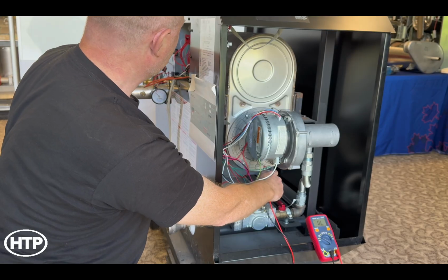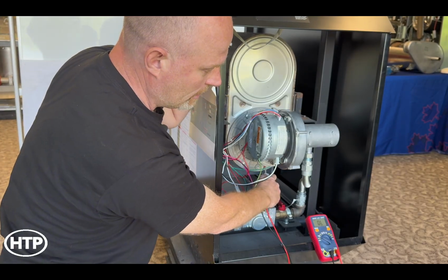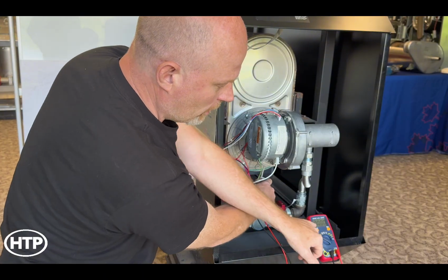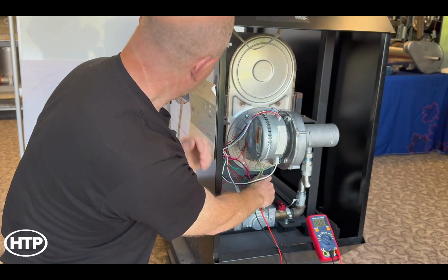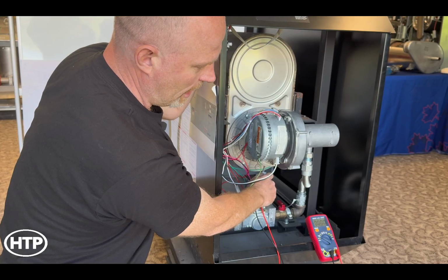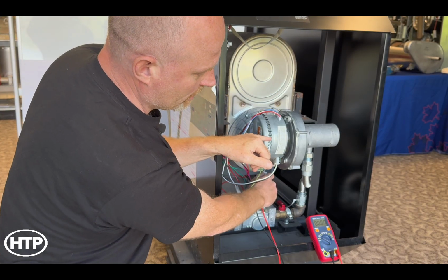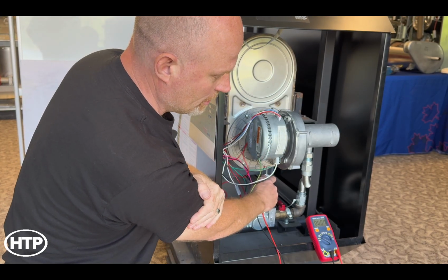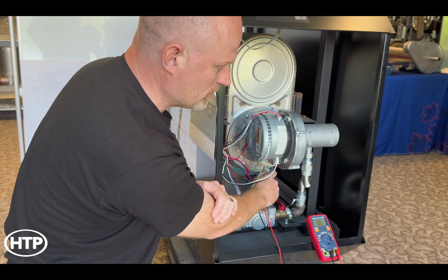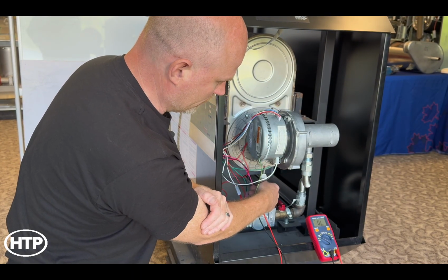So next thing I'm going to do is give this a call for heat. Hear the fan spool up. Hopefully you heard that little clunk. And now the call for heat's gone. We'll wait for this to slow down. The beeping's continuous, and then there we go. The flapper just closed again, and the circuit opened.